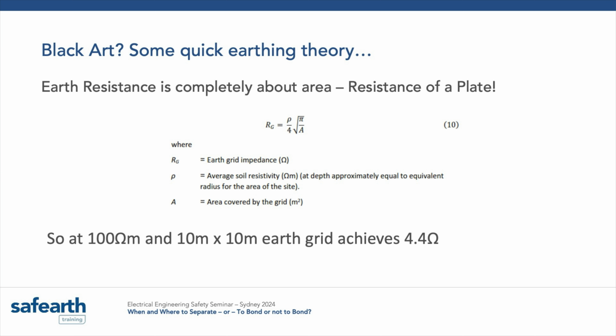All right, a little bit of theory real quick, just to give you guys a bit of a helping hand in the right direction. A black art? Actually, I think it's really quite straightforward. It's really Ohm's law. The earth resistance of a grid is entirely about area. Absolutely area. The resistivity of the soil, sure, we can measure that, or we can guess it, or we can use a previous report and say, well, it's going to be between this and that. It might be 100 ohm metres, it might be 10, it might be 500, who knows, depends on where you are. But if you know the soil resistivity and you know the size of your grid, you can very quickly come up with a calculation that tells you that the earth grid's going to be about 4.4 ohms. It's pretty accurate, 4.4 ohms.